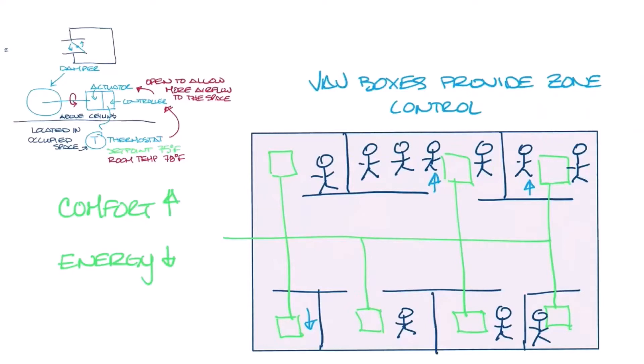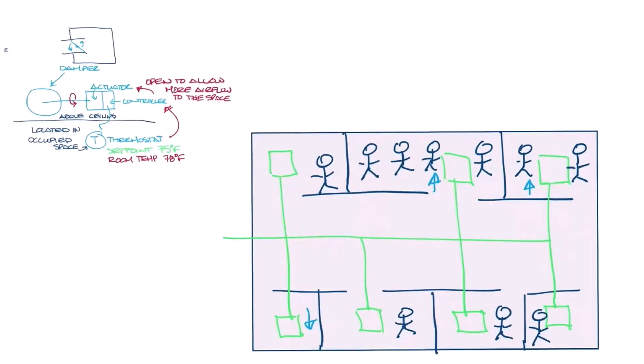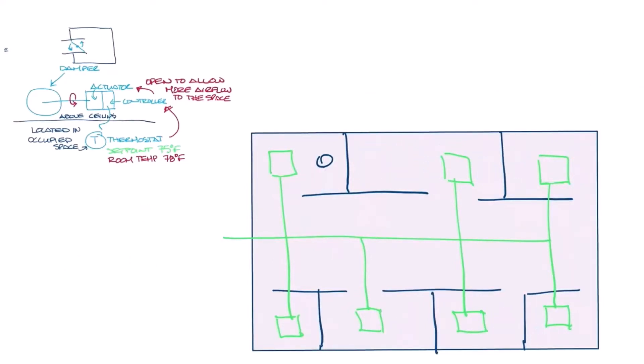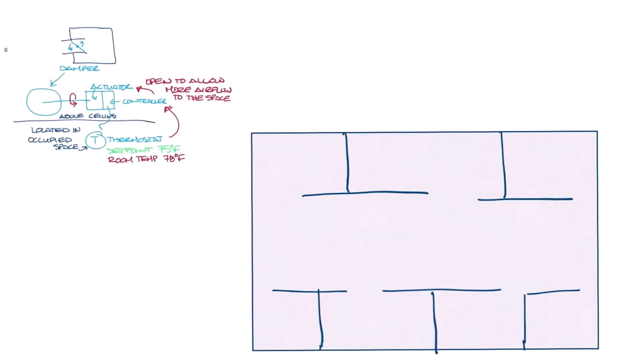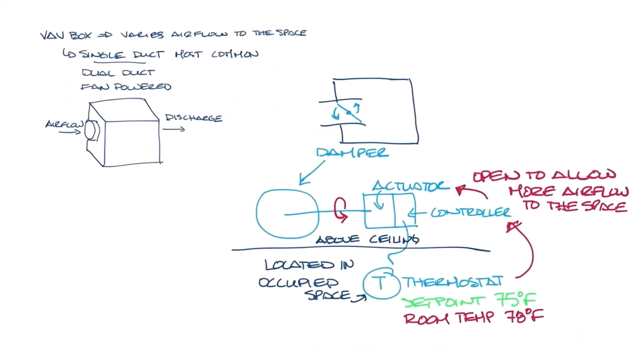So let's start by rewinding that last video a little bit so I can add in the flow sensor to the components of the VAV Box. The flow sensor lives in the inlet of the VAV Box. It's connected to the controller. When I said that the controller sends a signal to the actuator to open to give more air, the signal from the flow sensor is what the controller is using to determine how much airflow is moving through the VAV Box.